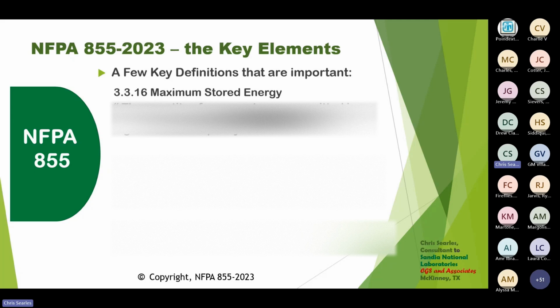Okay, maximum stored energy. This is a term that's important to understand as well. It's the quantity of energy storage permitted in a fire area prior to that area being considered a high hazard occupancy. I'll show you a chart in a minute that defines that a little better. This term was added into the 2023 edition.